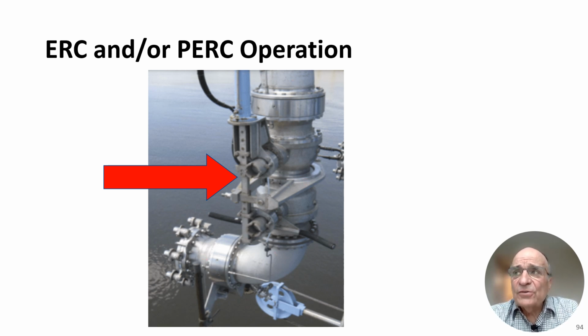I mentioned this earlier because these are quick acting. They typically actuate in about 15 seconds time, and you have to make sure that that timing is not such that it would cause a Joukowsky type water hammer, or fluid hammer, I should say.